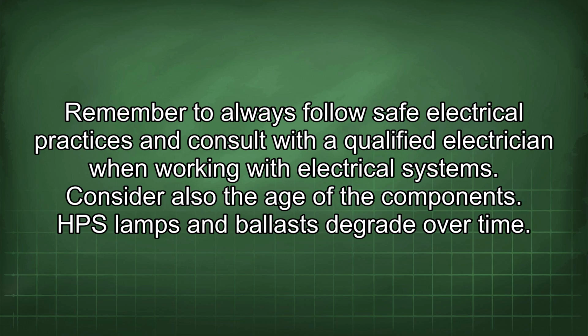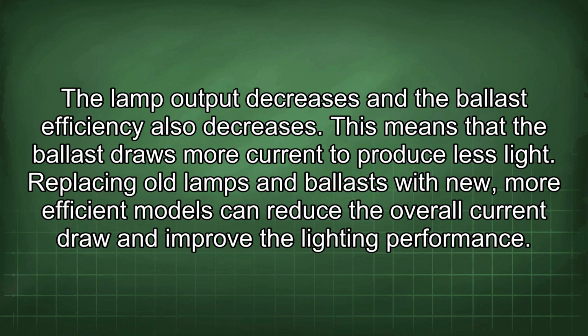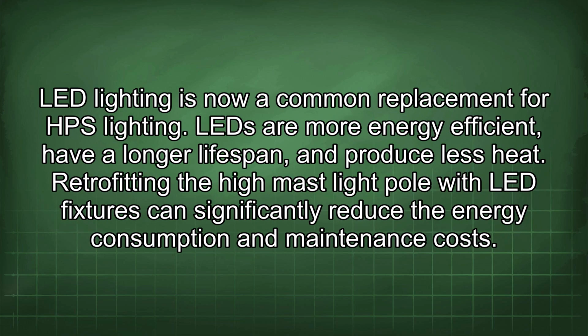Consider also the age of the components. HPS lamps and ballast degrade over time. The lamp output decreases and the ballast efficiency also decreases. This means that the ballast draws more current to produce less light. Replacing old lamps and ballasts with new, more efficient models can reduce the overall current draw and improve the lighting performance. LED lighting is now a common replacement for HPS lighting.